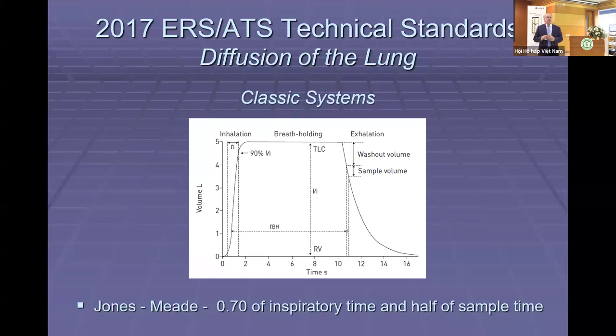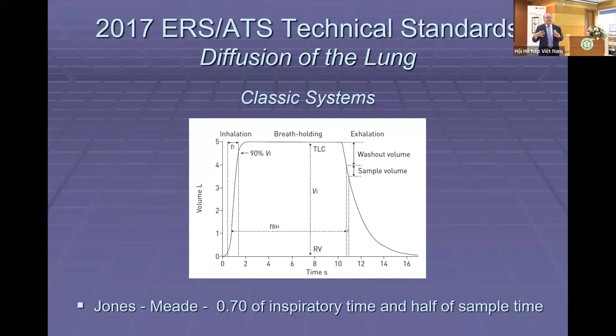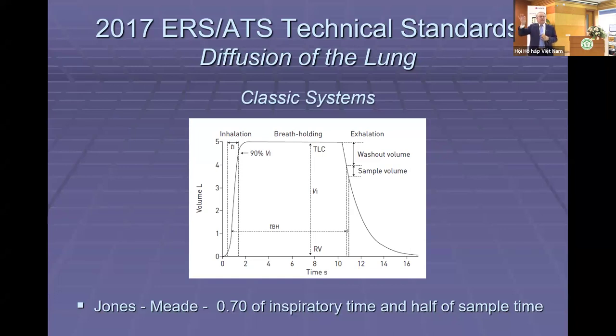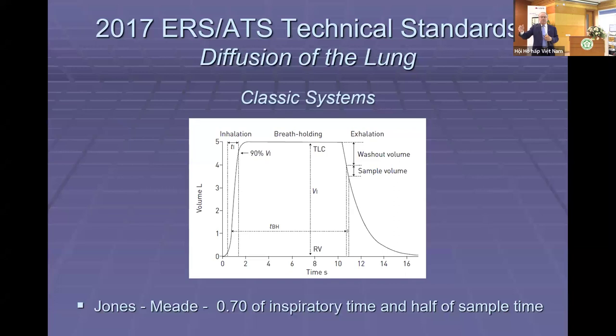The breath-hold time includes about 70% of inspiration, the full hold period, and a little bit of exhalation because you still have gas in the lungs. So if I set my system to hold for 10 seconds, it will calculate a breath-hold time larger than that. Oftentimes, people set their lockout time at maybe 9 seconds — accounting for 70% of inspiration plus a little expiration — so that the calculated breath-hold falls within the 8–12 second window.